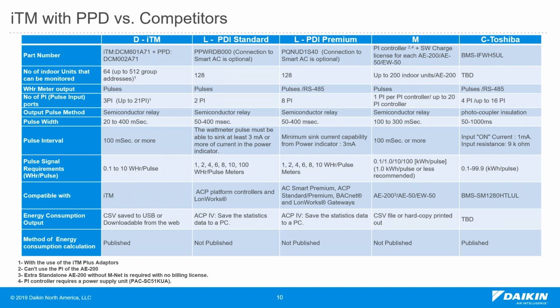If you look into the way that they integrate the energy meter to their controller, most of them use pulses, the same as our ITM requires pulse output from the energy meter, and that will be tied into the centralized controller. LG Premium can use RS485 connection and also Toshiba. How many pulses can we add to the system, or how many pulse inputs? An ITM itself has 3 pulse inputs. I think the LG PDI Premium can do 8 pulse inputs.